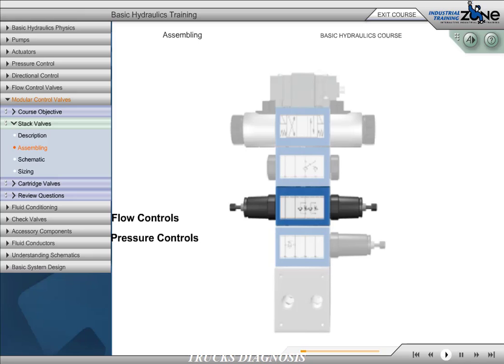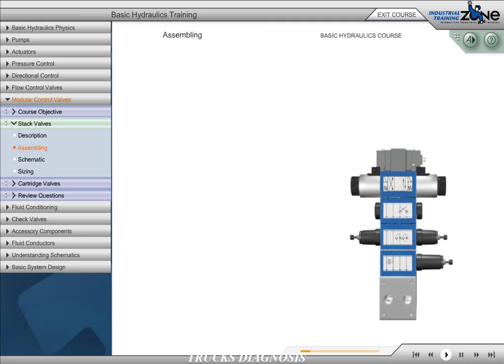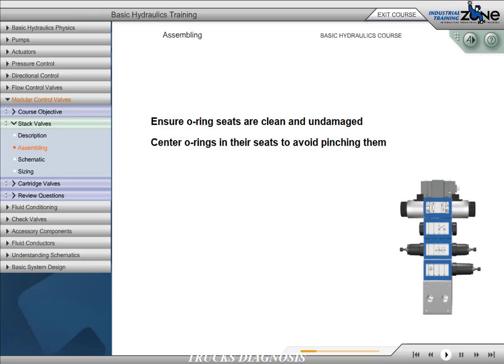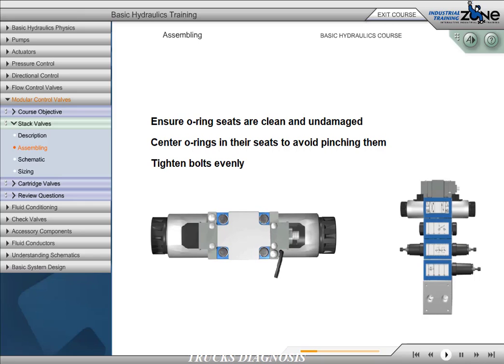The directional control valve is always located on the top of the stack. The relief valve should be placed at the bottom of the stack next to the subplate. Flow control valves and pressure control valves are placed between the relief valve and the directional control valve. Using proper procedures when assembling stack valves will produce a leak-free circuit. Clean and check all O-ring seats for damage, center new O-rings in each seat, and alternately tighten the mounting bolts until all bolts are properly torqued.